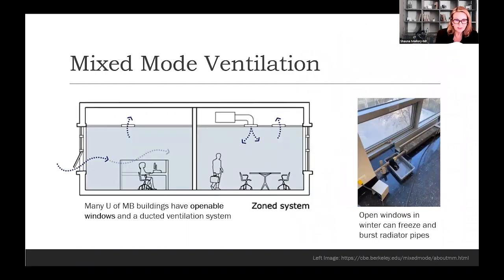Many University of Manitoba buildings have openable windows, in combination with mechanical ventilation systems. And in engineering and architecture talk, this is called a mixed mode ventilation system. So obviously opening a window is a really great idea to increase the amount of fresh air, and the air will be naturally drawn into the space. And then, as you can see in this diagram on the left, it'll be drawn up into the plenum space because that area is being basically sucked out by a fan as part of the mechanical ventilation.